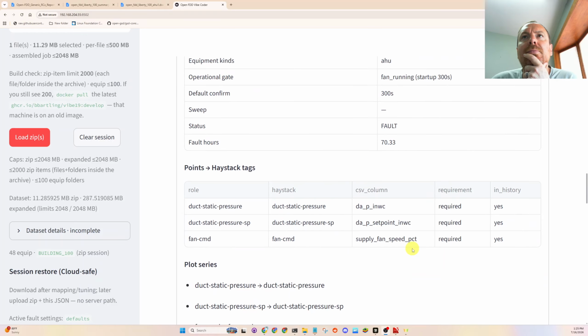Let's see, where was that? Fault hours, 70 hours. 70 hours of time this 100 horsepower fan ran wide open because it's not able to make its static set point for some unknown reason. I think this was due to, we talked about this briefly, that the chiller and the air handling units are on schedules. So the chiller shuts down before the air handling unit does, and the air handling unit needs cooling, and when it doesn't have cooling, that's when VAV boxes start opening up. Duct static pressure goes down in the system, and before you know it, these fans are running wide open. So this is an energy savings opportunity here too.